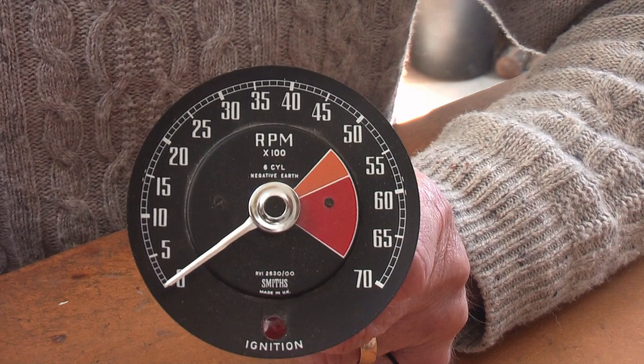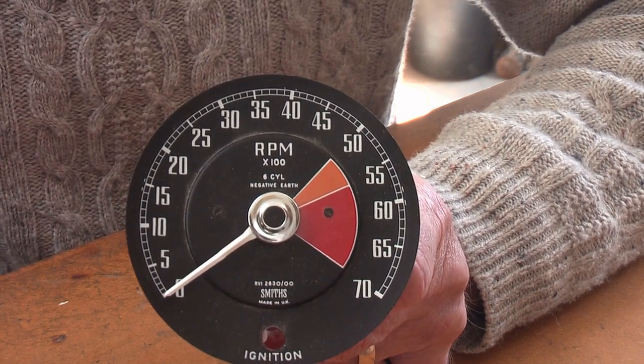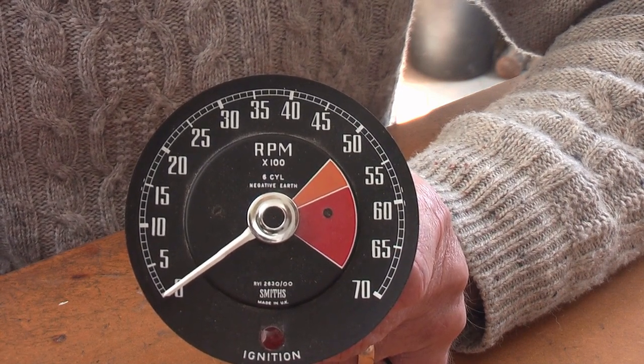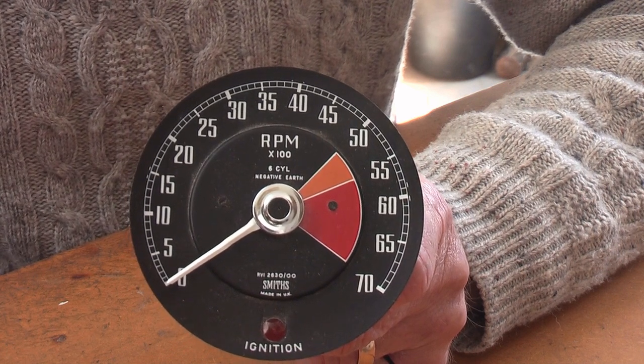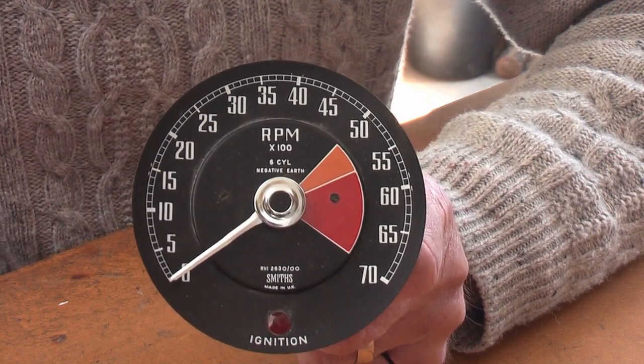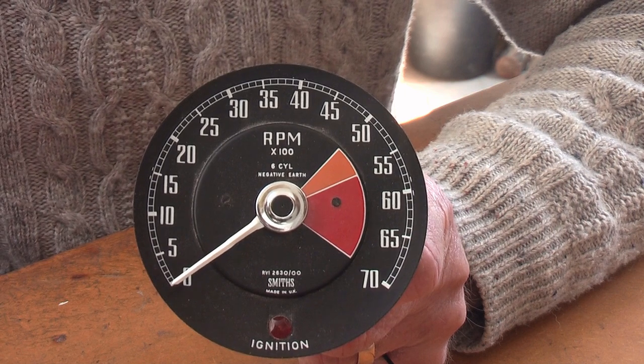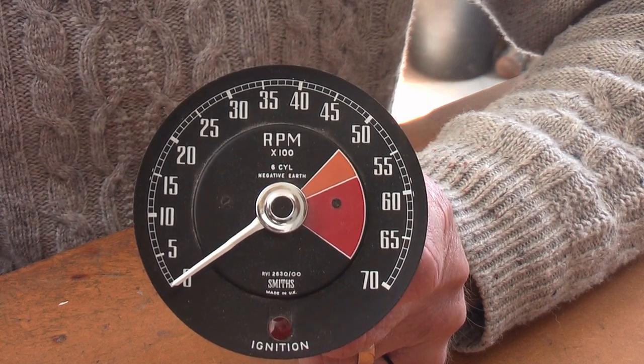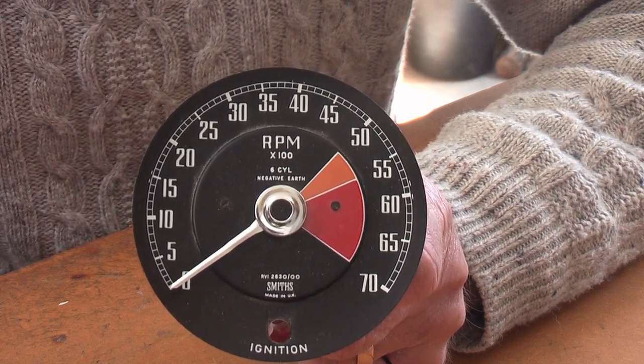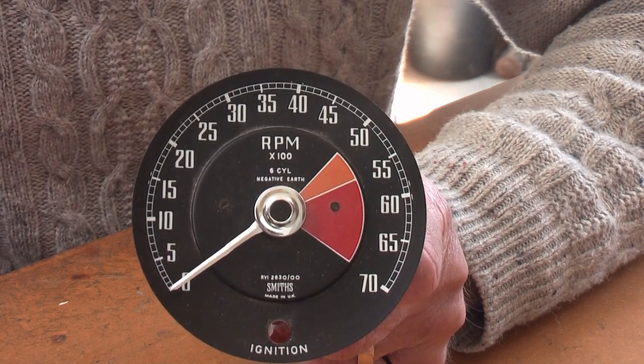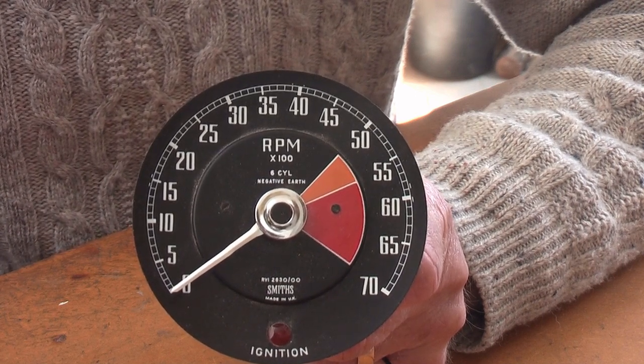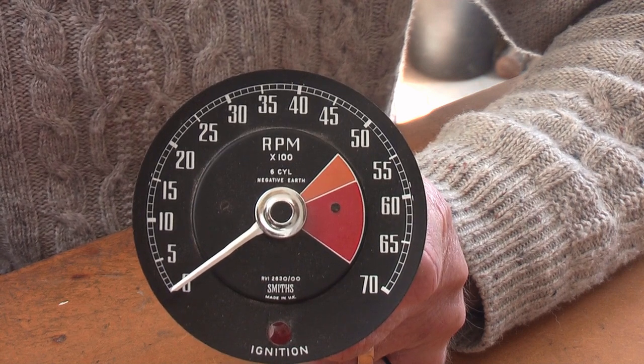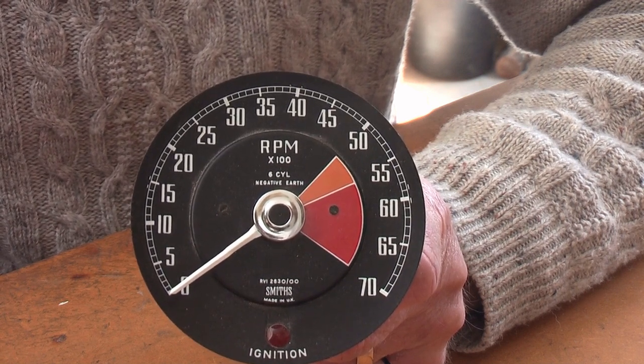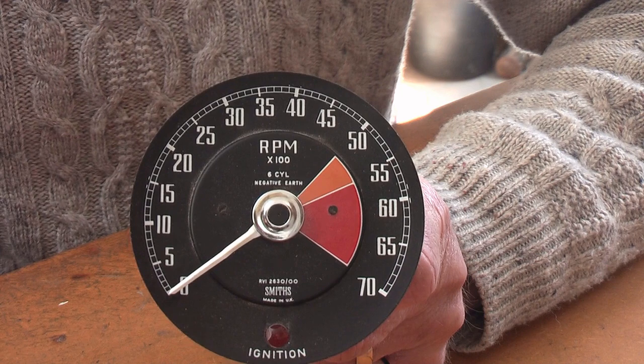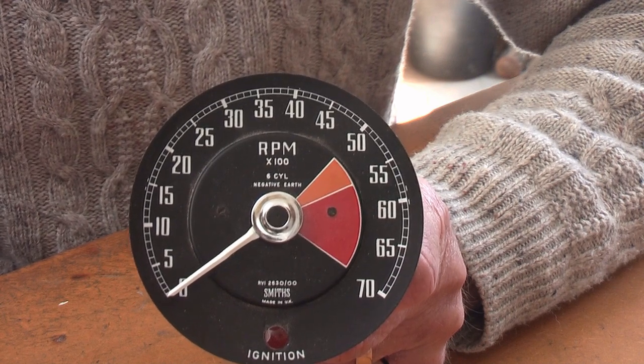One thing that can occasionally happen is that when you do the calibration, the needle does move, but not as you expect. If you've looked at our calibration videos, you'll see that when you release the calibration button, the needle should move very slowly but smoothly around the scale. But occasionally it can move erratically — it might stick and then suddenly jump, or get to a point and not move any further, rather than moving smoothly.